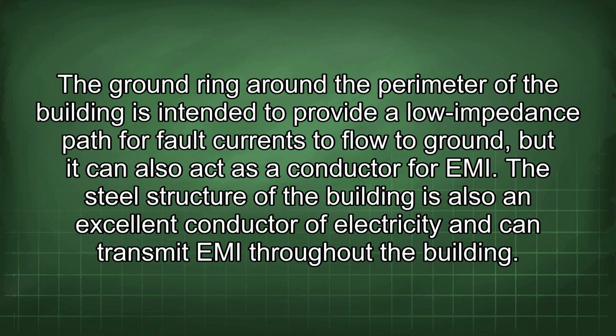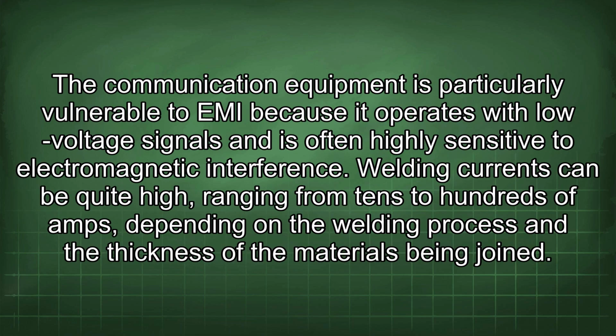The ground ring around the perimeter of the building is intended to provide a low impedance path for fault currents to flow to ground, but it can also act as a conductor for EMI. The steel structure of the building is also an excellent conductor of electricity and can transmit EMI throughout the building.